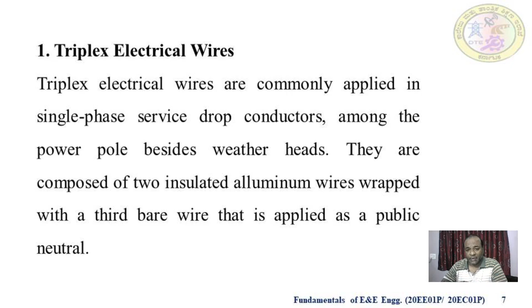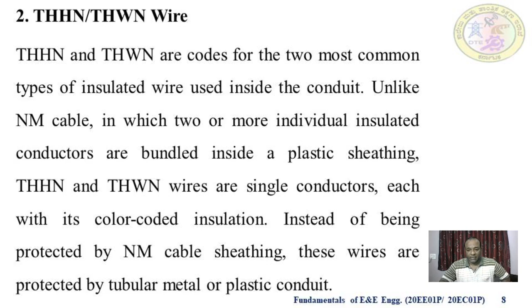THHN, THWN wire. THHN and THWN are codes for the 2 most common types of insulated wire used inside the conduit. THHN: T means thermoplastic, HH means highly heated, N means nylon coated. And THWN: T means the same, H also the same, and W means wet. Unlike NM cable, non-metallic cable, in which 2 or more individual insulated conductors are bundled inside a plastic sheathing, THHN and THWN wires are single conductors, each with its color-coded insulation. Instead of being protected by non-metallic cable sheathing, these wires are protected by tubular metal or a plastic conduit.